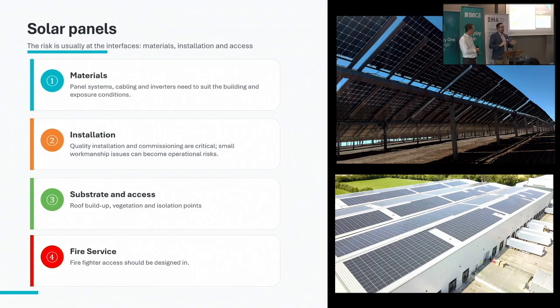Buildings are slightly different in that you've often got them strapped to the top of a building. Again, the risk is not the solar panels - the risk is actually you get an electrical short and that starts a fire within the building. So it's being able to manage that, making sure you've got isolations for the fire brigade to be able to shut it off when they get there.